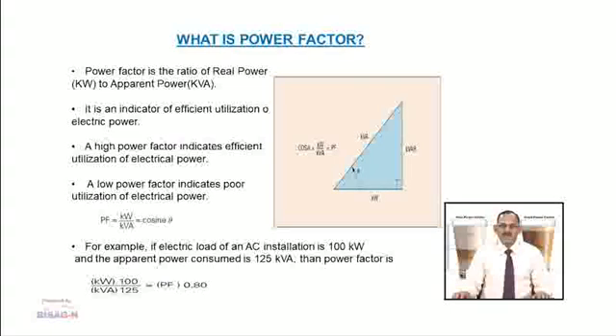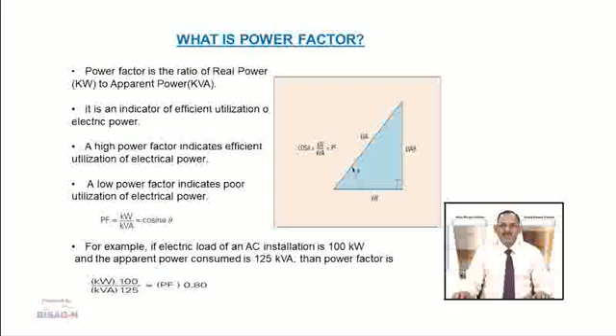For example, if the electric load of an AC installation is 100 kW and the apparent power consumed is 125 kVA, then power factor = kW / kVA = 100 / 125 = 0.80. From the power triangle we can see that kW is the actual or working power, kVA is the apparent power, kVAR is the reactive power, and power factor cos φ = kW / kVA.